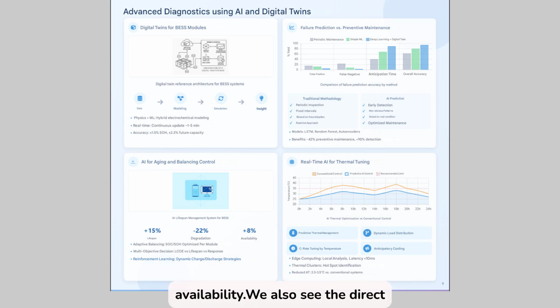We also see the direct application of AI in predictive thermal management, such as thermal control curves comparing conventional control, predictive AI control, and the recommended thermal limit, approximately 40 degrees. Some features include local analysis with latency less than 10 milliseconds, edge computing, dynamic load distribution, anticipatory cooling by predicting thermal peaks, and detection of thermal clusters or hotspots. Some results can include a reduced temperature increase of between 0.3 and 0.5 degrees compared to conventional systems.